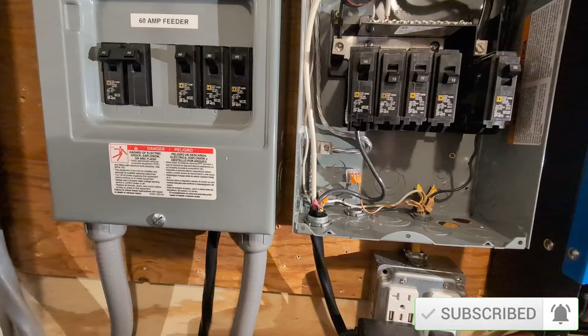And now, in the event that I need to do work on the inverter, on the Victron system, I can have it stop providing the house with power and just go directly off grid. Again, this is limited to a 40 amp breaker. The house never pulls more than about 30 amps at any one time. I don't have a lot of stuff going on there. So alright, let's get this cover back on and make it safe, and we'll move on from there.